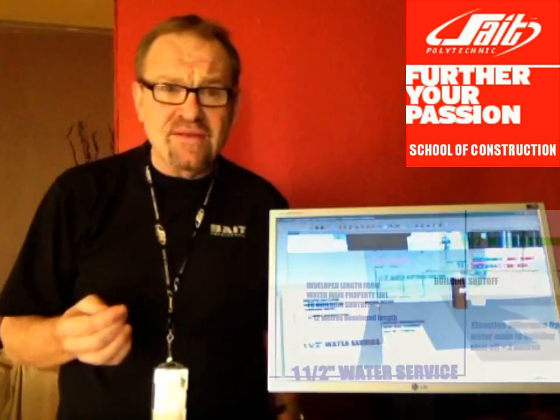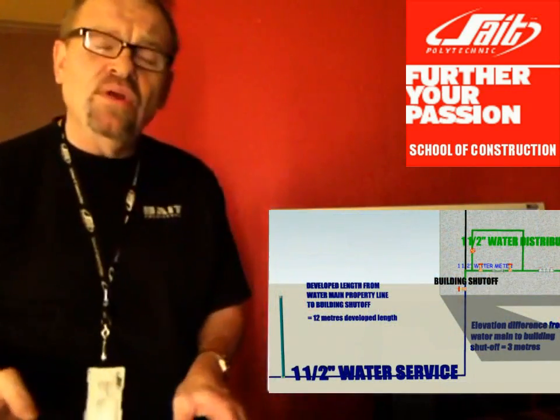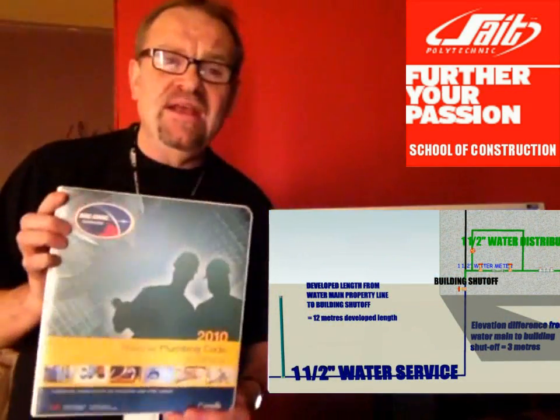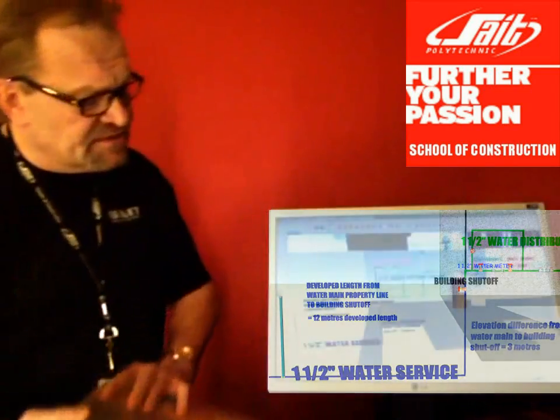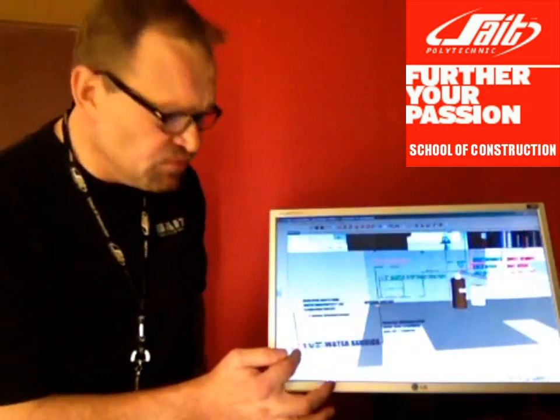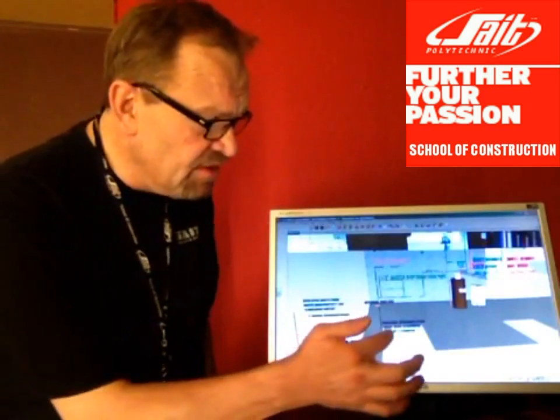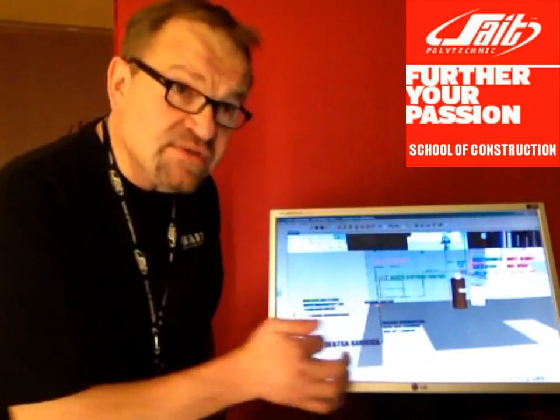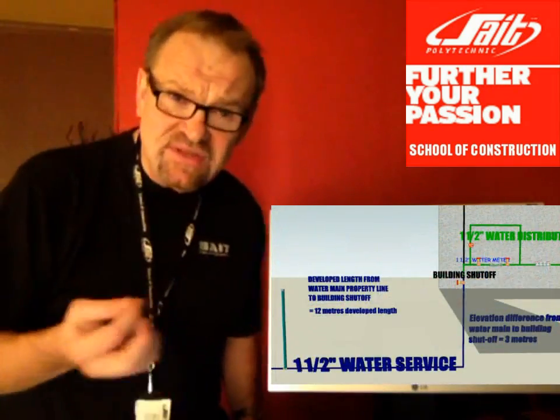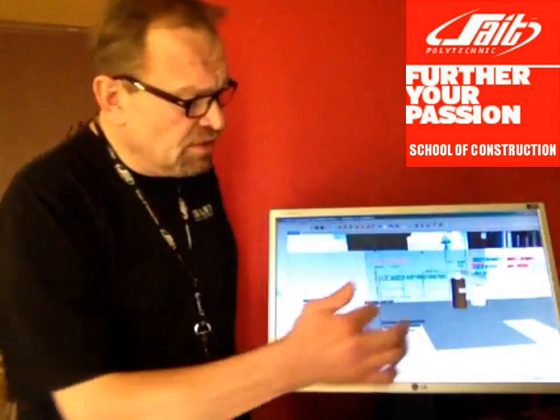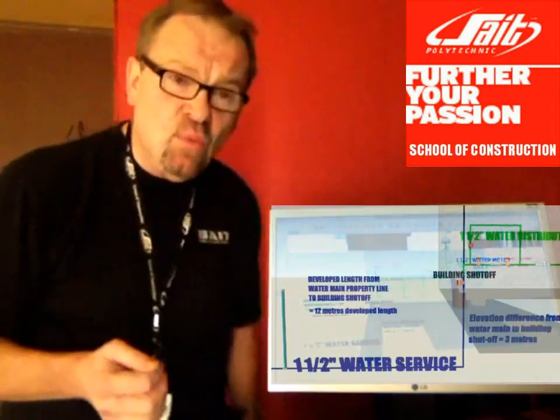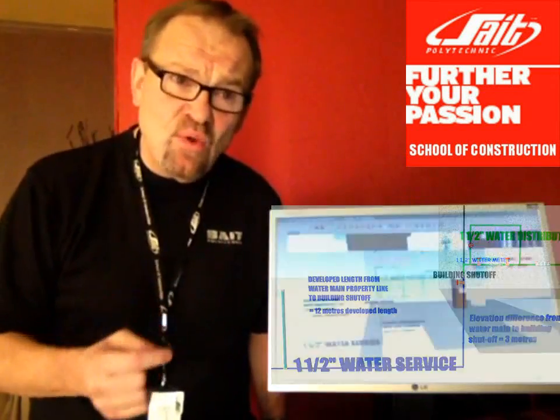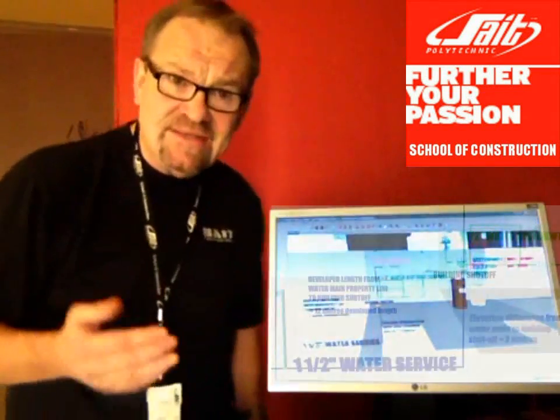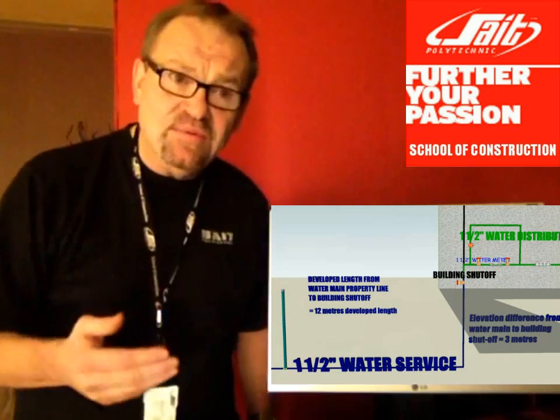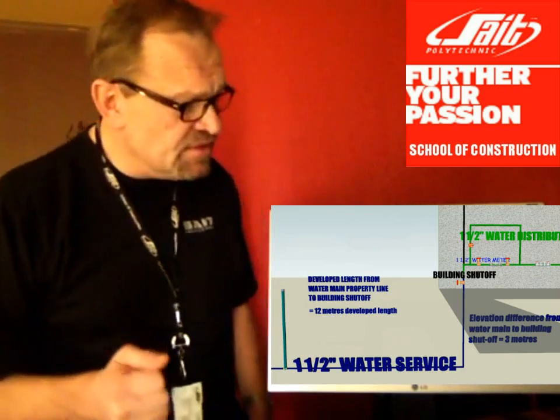In Part 1, according to the 2010 National Plumbing Code, we had sized the water service, which was located by the property line up to the main building shutoff outside of the building, as 1.5 inches. We sized this according to peak demand. We had also sized the green pipe, the water distribution entry pipe by the water meter, also as 1.5 inches by tables 2631 and 2632 in the National Plumbing Code.